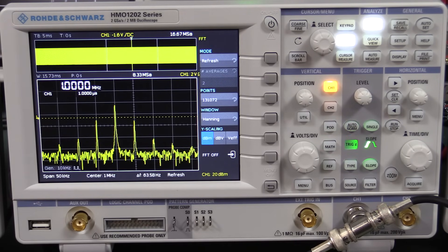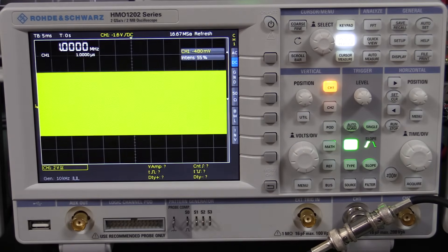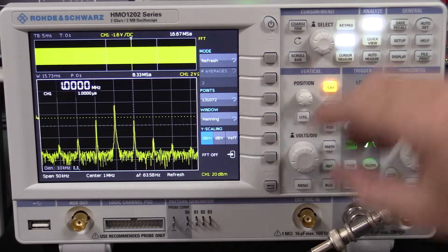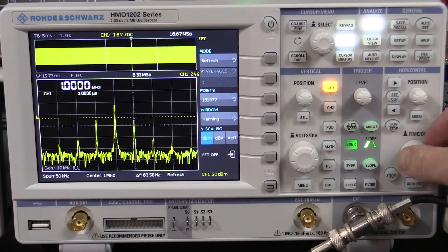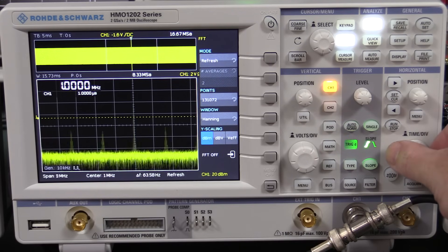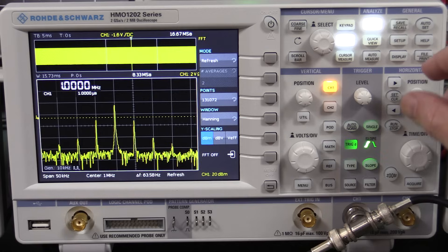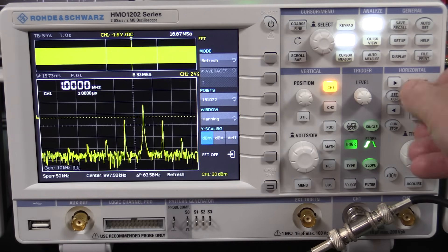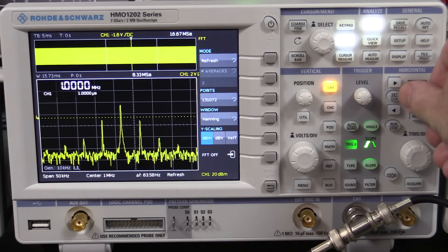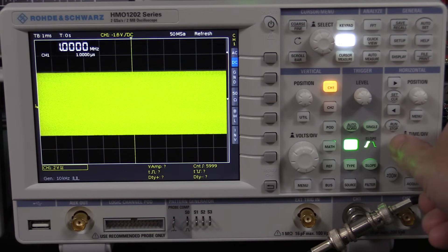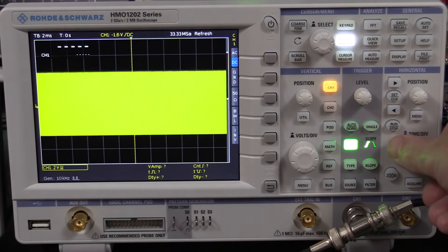Another thing I like about this scope is when you turn FFT mode on, you don't have to go digging through menus. The time-per-division knob now directly controls the FFT span, and the horizontal position control pans the FFT — absolutely fantastic and incredibly intuitive to use. If you want to adjust the time base, you turn FFT off, adjust, then switch back.